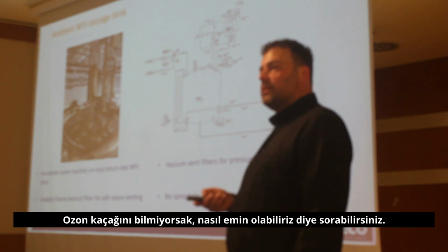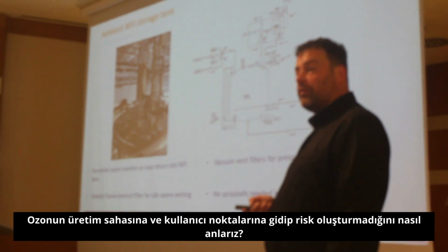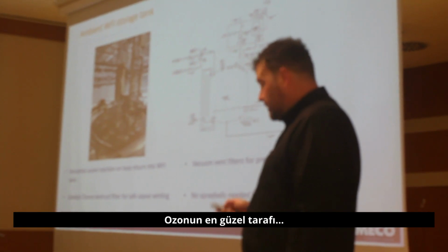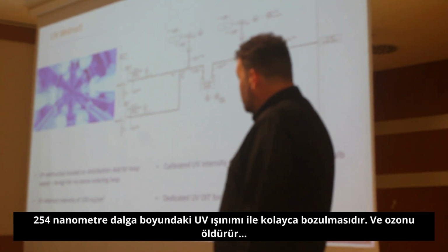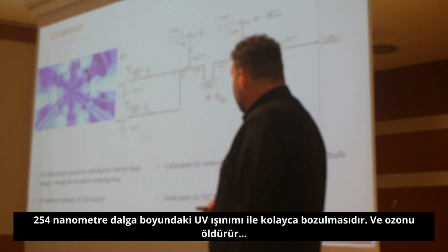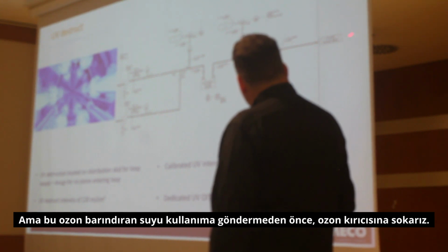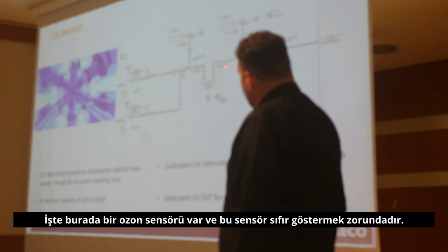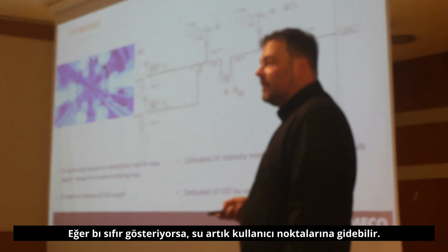Now, if you don't know ozone, you probably ask, how do we keep it safe? How are we ensuring we do not send ozonized water into our plant, into our loop, and risk contamination of our products at our use points? So this is basically the beauty of ozone: it is easily destroyed with UV light. It's usually 254 nanometer, which is the wavelength that kills ozone. That's why on the typical distribution system here you have your pumps that send the water out into your factory, but before it goes there, it goes through the ozone destruct UV system. That's this. So here is another ozone measurement point. That measurement will have to show 0 ppb. And if it does that, the water goes to the use points.